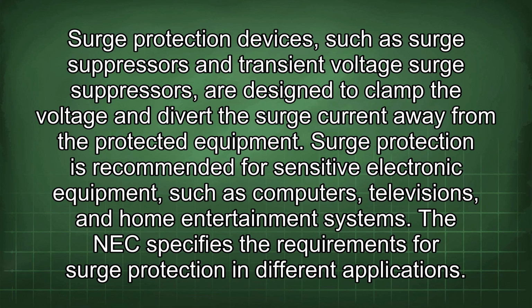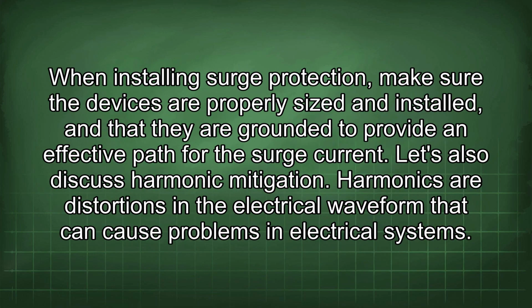Surge protection is recommended for sensitive electronic equipment, such as computers, televisions, and home entertainment systems. The NEC specifies the requirements for surge protection in different applications. When installing surge protection, make sure the devices are properly sized and installed, and that they are grounded to provide an effective path for the surge current.